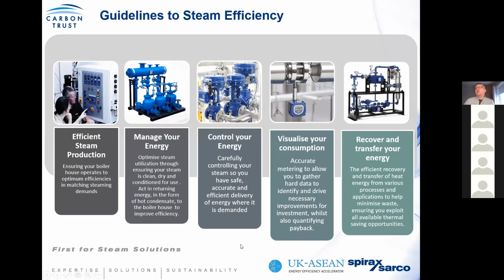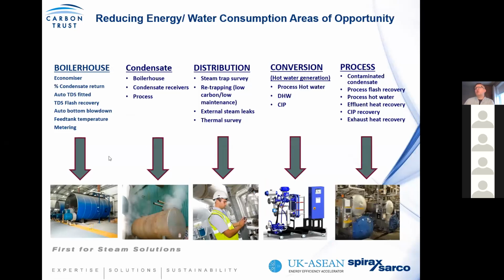So again, from our own experience, when you consider what we've identified through our audit process, you can see that realistically, these are the type of savings that can be achieved through the different systems, from generation right through to the actual process itself. Now, when we talk about the process itself, we're finding this is where waste heat recovery comes in. So for example, you have retorts which may reject a lot of heat to atmosphere. That heat can be recovered, for example, to preheat boiler makeup water. And also when we look at distribution losses, the traps, the vent steam, etc. And again, we will demonstrate how you can recover that energy.